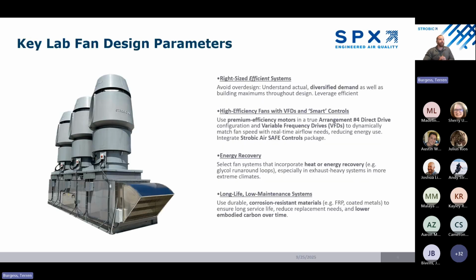So when we talk about designing sustainable lab exhausts, right, the first step is to right-size the system. Far too often, these systems are over-designed to meet these theoretical maximums, right? So instead, what we really want to do is design around actual diversified demand while still accounting for those peak demand building spikes. That's going to help us avoid wasted capacity, unnecessary energy use, and make sure that we have the right-sized equipment for our application.